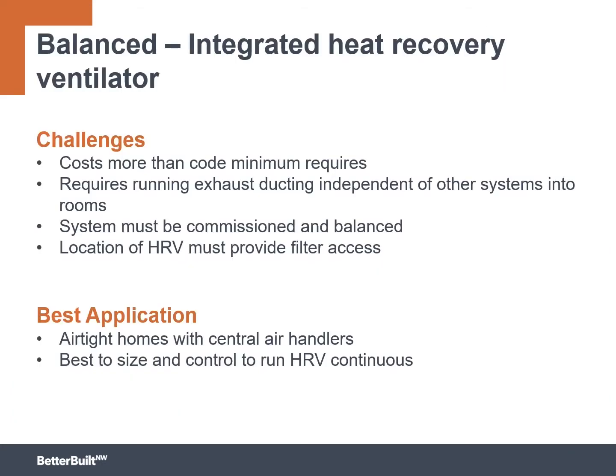Again, we have both challenges and benefits, right? So the benefits we've already basically covered. It's balanced, it's distributed. You can select a variety of different heat recovery ventilators. You may even have multiple ways to do filtration, both filtration in the HRV and filtration in the home. So in wildfire areas, you might have double the benefit. But there are also some challenges to this system. Of course, it costs more than the code minimum, and it does require still running the exhaust ducting independent of the other systems. We're saying that half of the system should still be ducted independently.